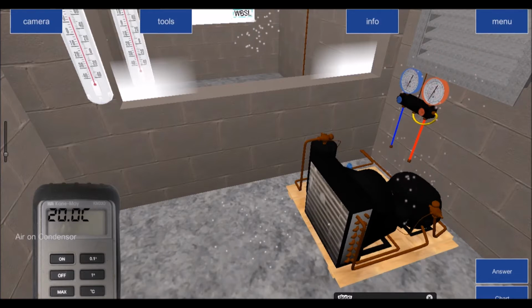The air coming off the condenser is going to be warmer because it's removing the heat from the refrigerant. But in order for effective refrigeration to take place, so effective heat rejection, or efficient condensing of the refrigerant to take place, the temperature of the refrigerant needs to be between 10 to 20 degrees higher than the air temperature coming on. So remember, in order for heat exchange to take place, there must be a temperature difference, and therefore when manufacturers are designing air cooled, and I keep putting an emphasis on the air cooled because water cooled changes the rules, water cooled condensers are 10% more efficient than air cooled condensers.